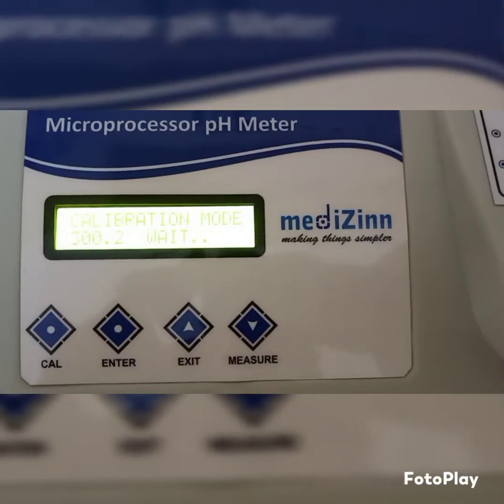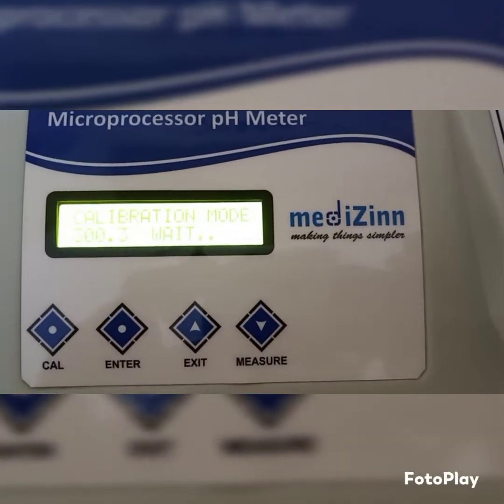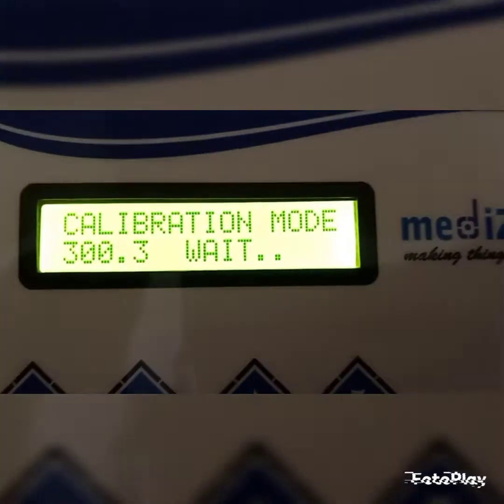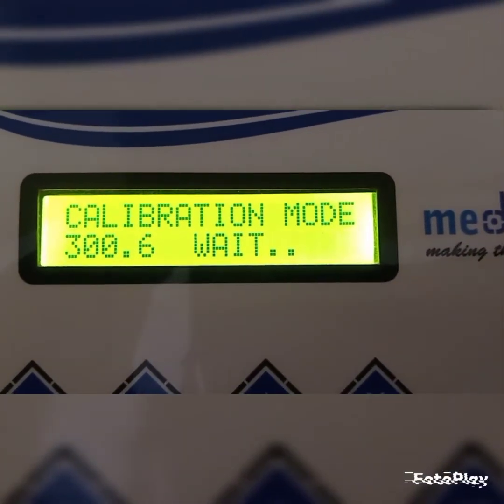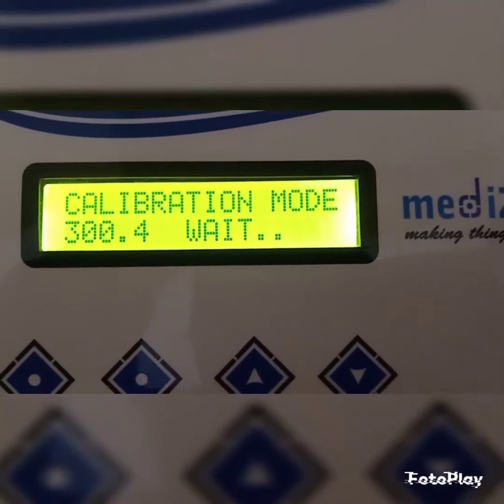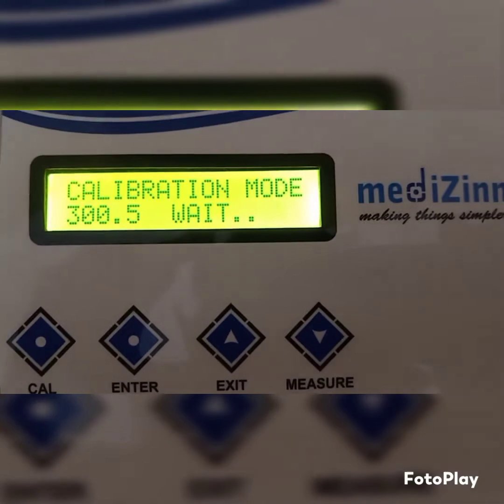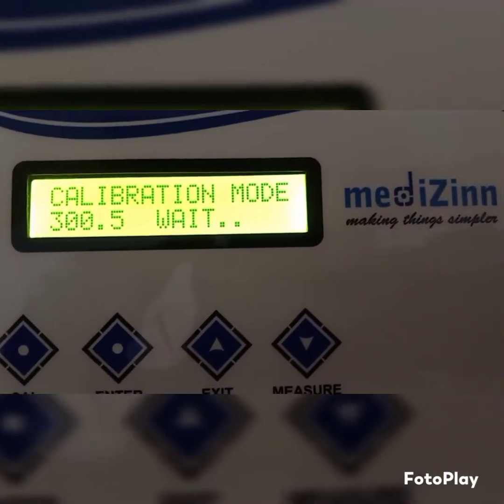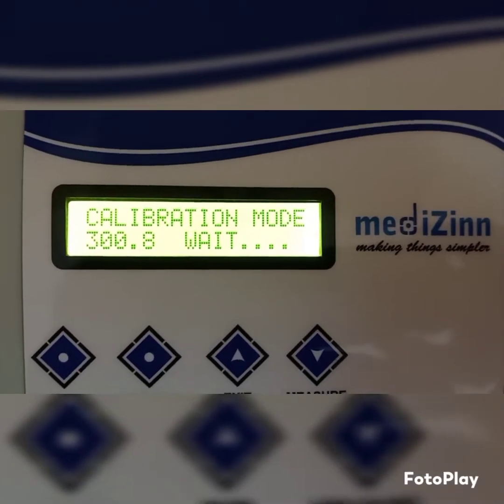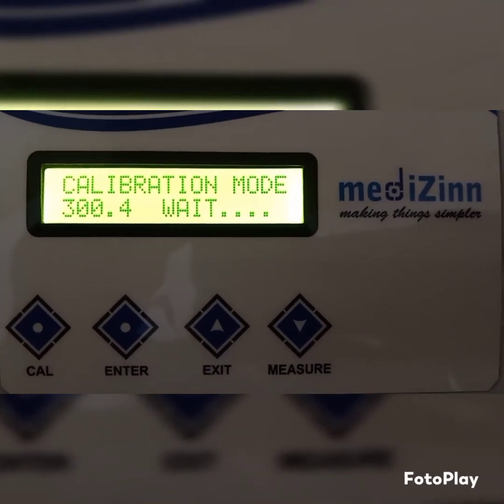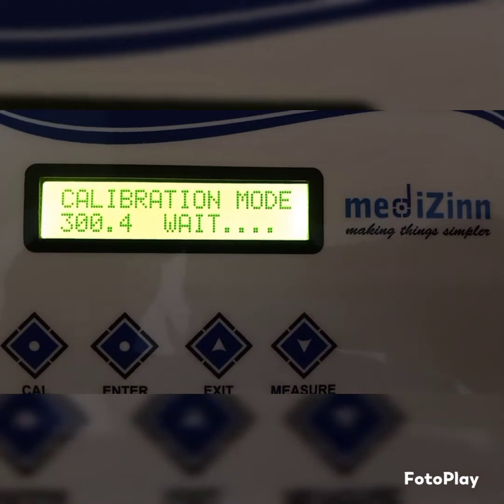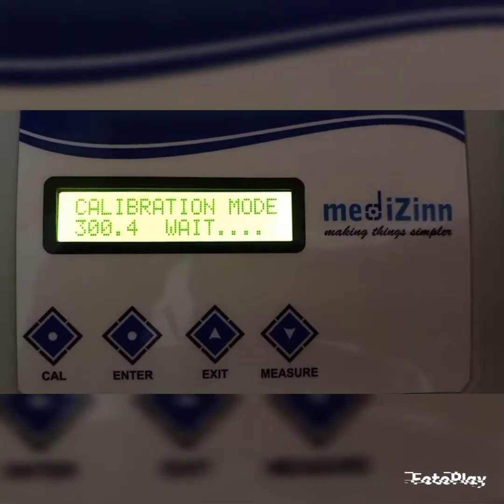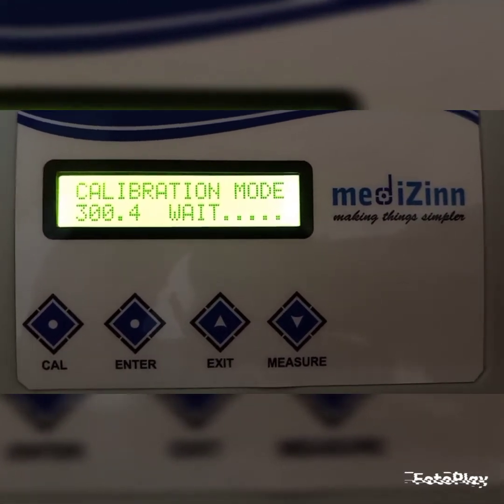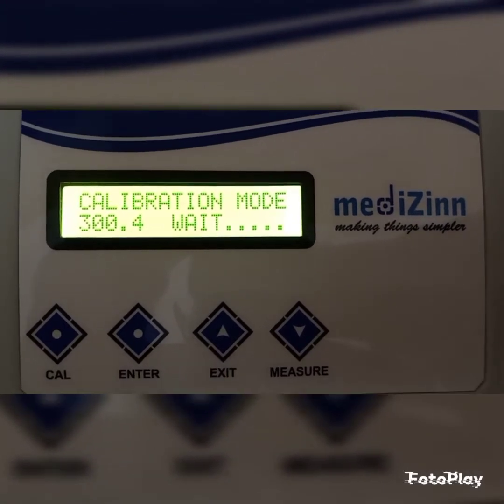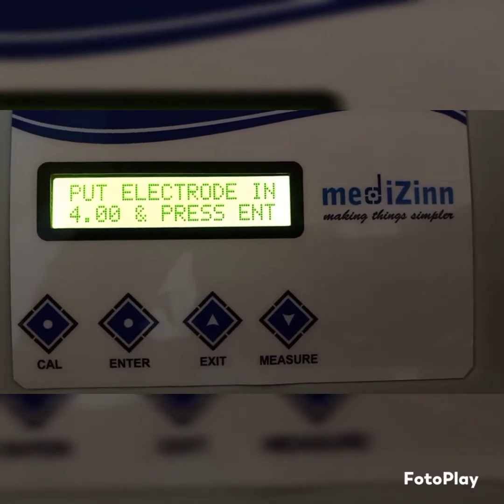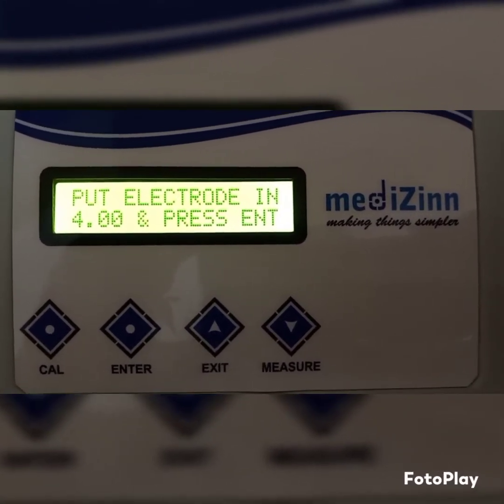This 300 showing some analog value corresponding to 1.68 pH. This must be stable during the calibration process. Right side dot may vary. So we have to wait for approximate 2 minutes for the calibration process over. Now 1.68 pH completed. Now display showing put electrode into 4 pH and press enter.